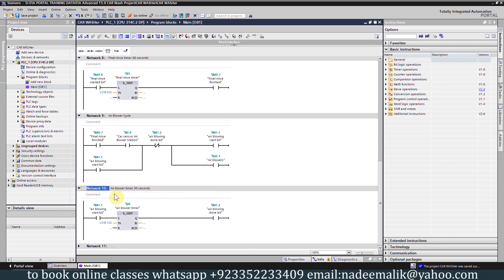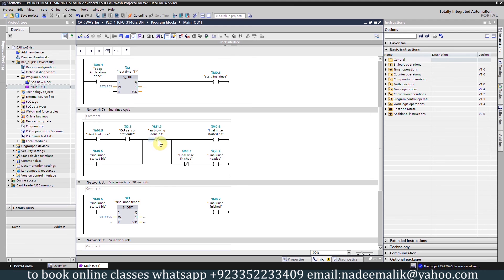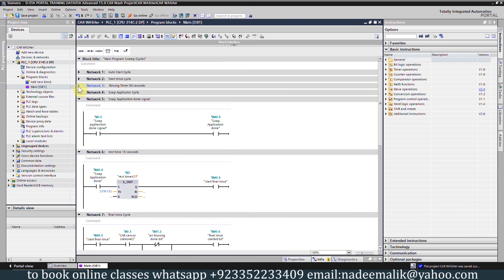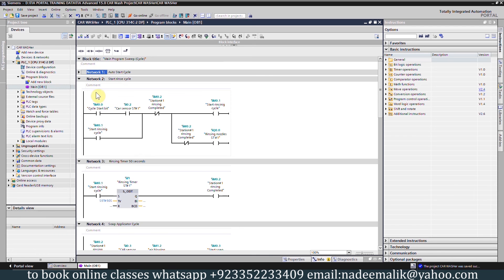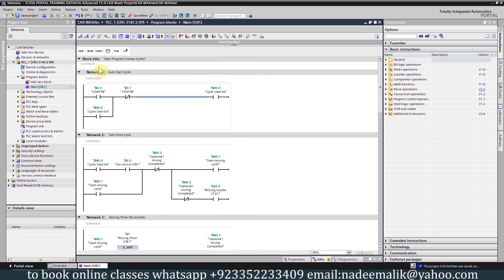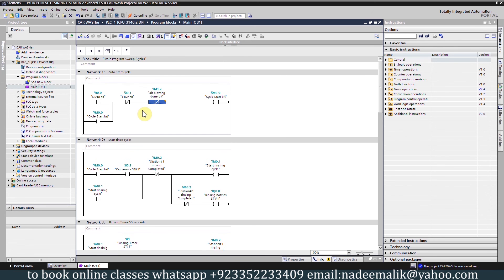In network number 10 we have an air blower timer. Once bit M1.1 is on it will start timer T4 for 30 seconds, which will then turn on the air blowing done bit M1.2. A normally-closed contact of M1.2 is inserted here so once the timer is over this bit turns on, opening the contact and turning off the air blower and related bits. This same bit M1.2 is also used in the final rinse cycle to turn off M0.6, in the soap applicator cycle to turn off the start soap application bit, and to turn off the overall cycle start bit M0.0 when the final air blowing step is completed.